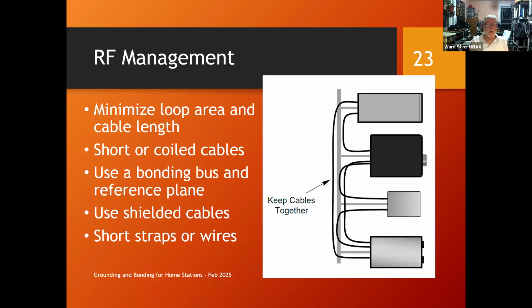Inside, however you have your bonding structure, here's an example with the pipe. You want to minimize loop area and cable length of all the cables connecting the different boxes together. The amount of voltage induced in a loop is directly proportional to area, so if you make the area small, you also make the voltage that causes current to flow in the loop small.